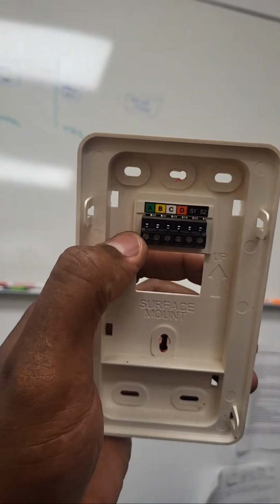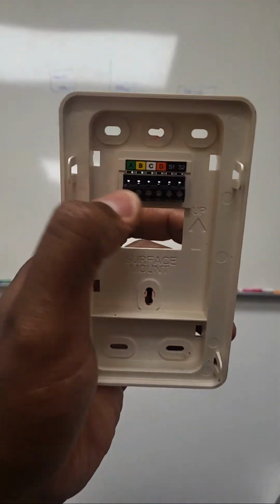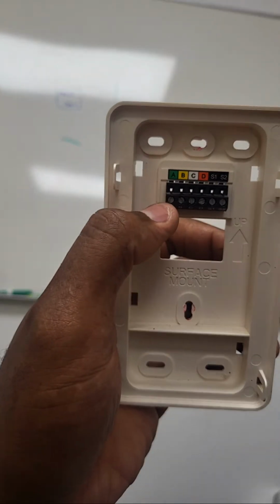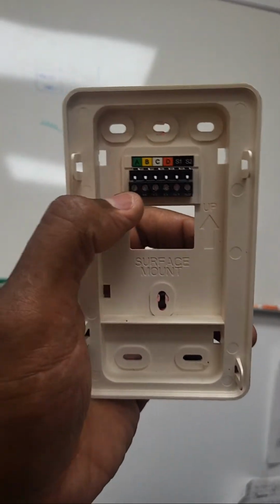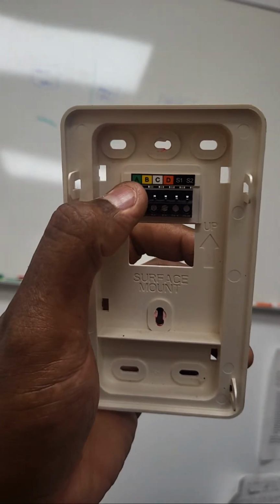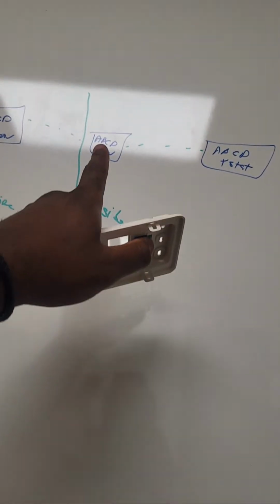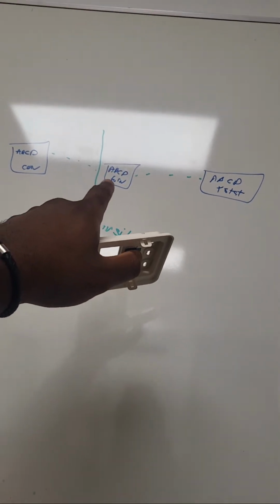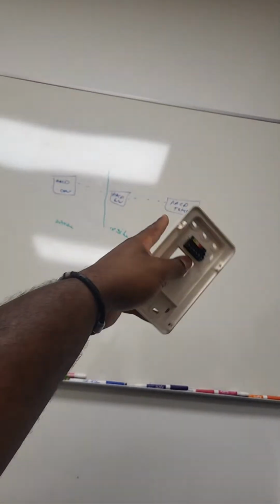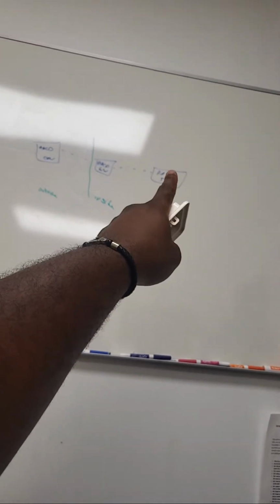And instantly, guys, knowing that I had power from C to D, I also checked my wires. With this, you want to make sure whatever wire you have connected to terminal A on the thermostat is connected to the same color wire that's going to A on the furnace. And that's very, very important. You guys heard me say this before, as far as with circuit board wires, for instance, the R, W, C, G terminals, whatever color wire you use, the terminals really don't matter. It's the color of the wire that really matters. You want to make sure that whatever color wire you have hooked up on one end is going to the same on the other end.